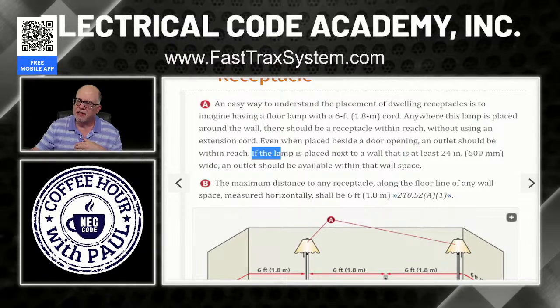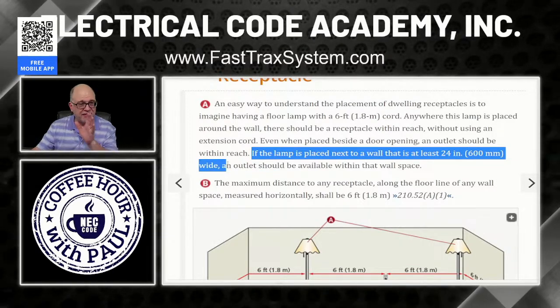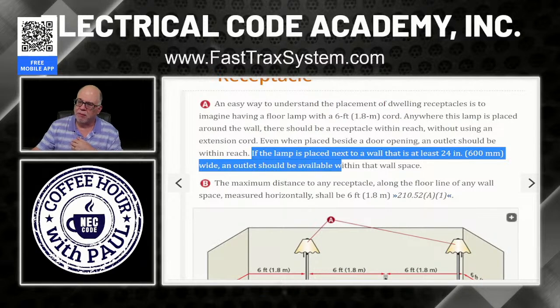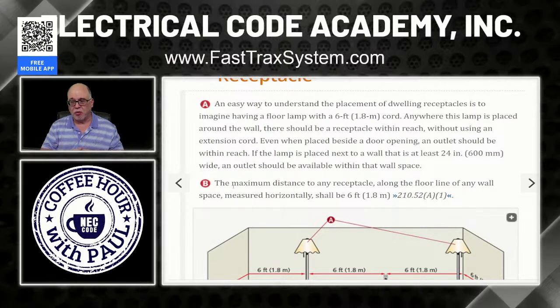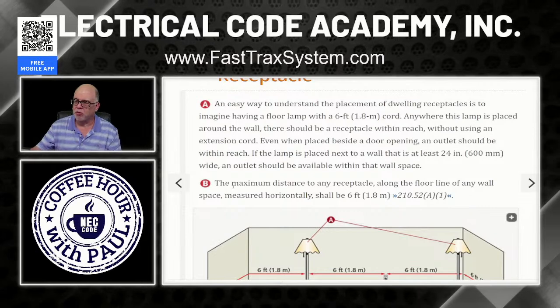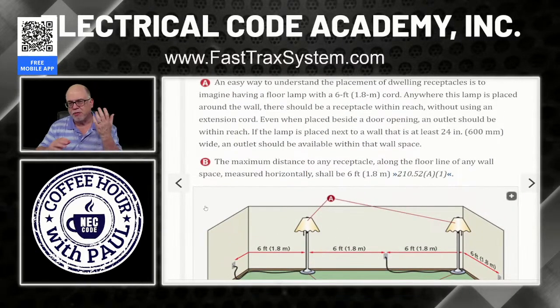It says, if the lamp is placed next to a wall at least 24 inches wide, so maybe that's the space between the entry into the bedroom and a closet, an outlet should be available within that wall space because, again, 2 feet or more requires an outlet. So maybe that is the perfect place to put a lamp. And that's why the code requires one to be there if it's 2 feet or more in wall space. Kind of see how all that works? It's all done for a reason, folks.